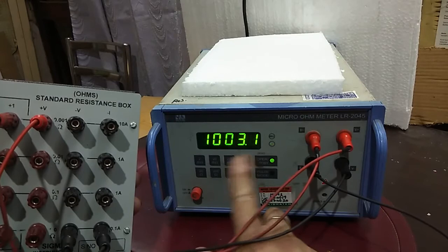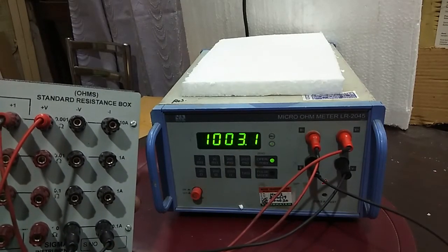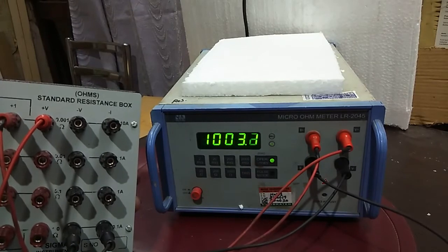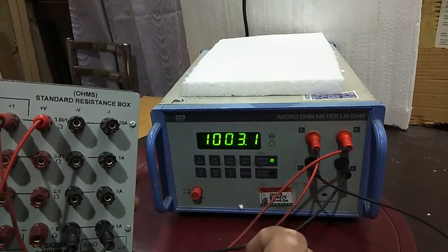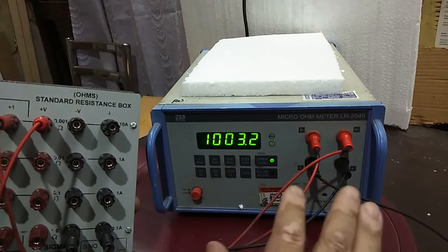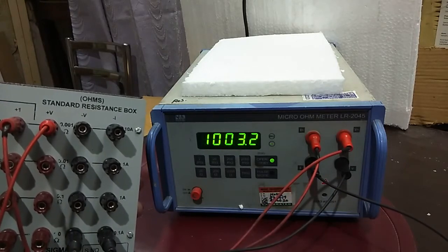So I have put a thousand ohm resistor and it is showing one double zero three point one. Four and a half digit results are good. The accuracy is point zero five percent in this model.